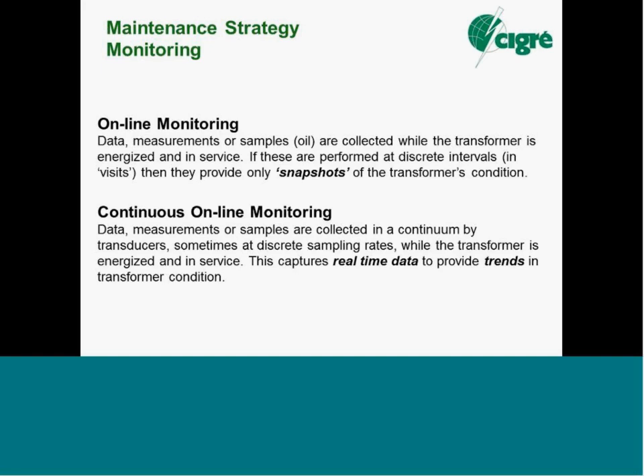So with visually inspecting the transformer operating online, or taking an oil sample with the transformer online, we are taking snapshots of the transformer's condition at discrete intervals. These inspections and oil samples are taken at discrete intervals. So it's important to remember these are snapshots of the transformer's condition, and if we want a continuum, if we want timely monitoring, then we have to move to continuous online monitoring, capturing real-time data and trends. Very useful, powerful, in trends in the change in state.